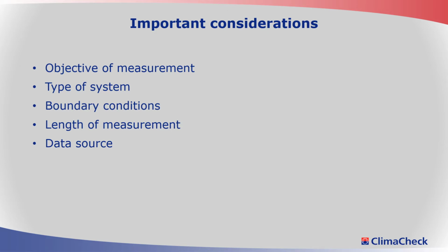If it's a problem that we're looking for, then we need to measure until that problem occurs. If we're looking at how the system operates during a week, if it has different fluctuations in the loads and different ambient temperatures, we need to include these in our measurement.